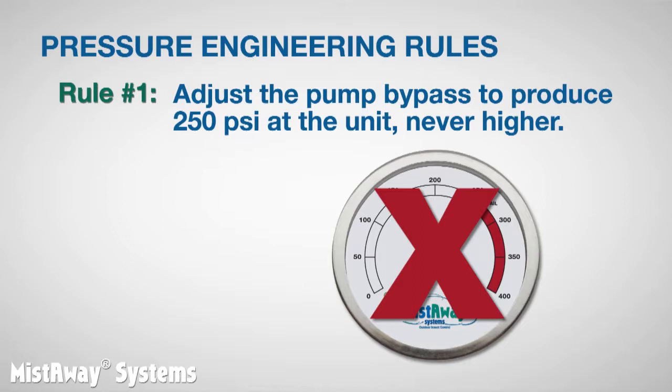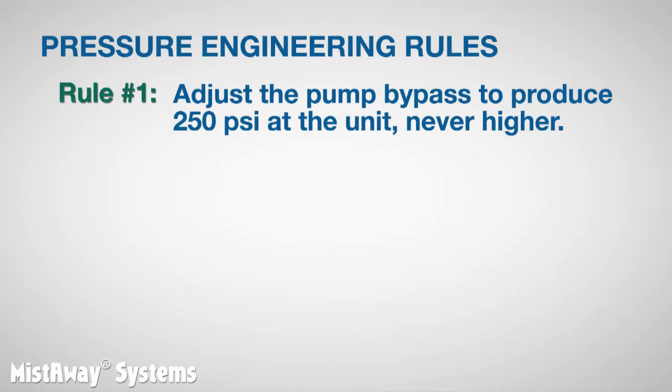Rather, you have too much pressure drop in your nozzle circuit and you'll need to rethink how it is plumbed. We'll talk about that in another video. Repeating rule number one for emphasis: adjust the pump bypass to produce 250 psi at the unit, never higher. Never higher.